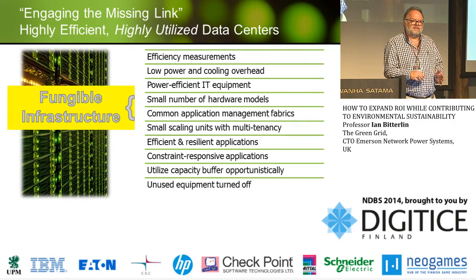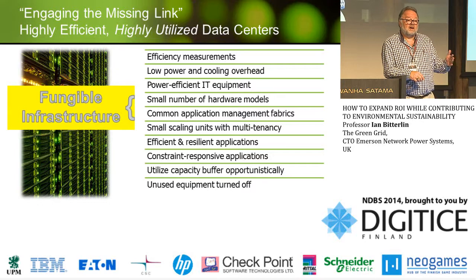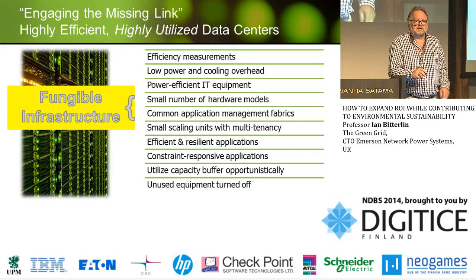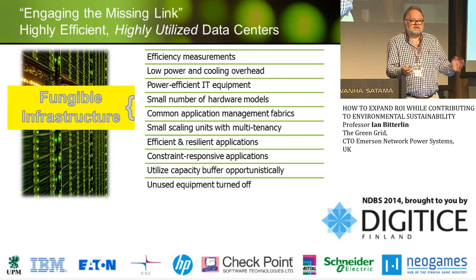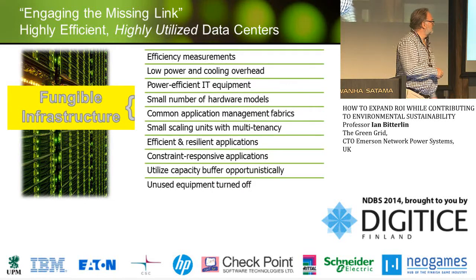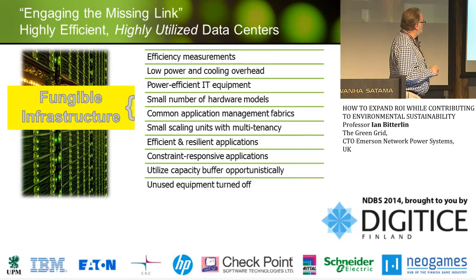The really important thing is not PUE. The really important thing is the utilisation of the IT hardware. Most data centres sit there idling, burning power, even with an efficient, low PUE. It's no use if your IT equipment is doing nothing, or close to nothing.